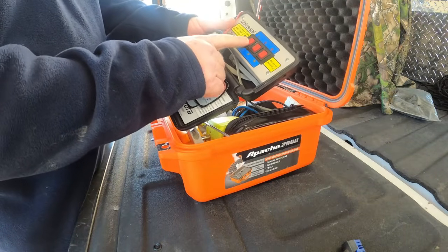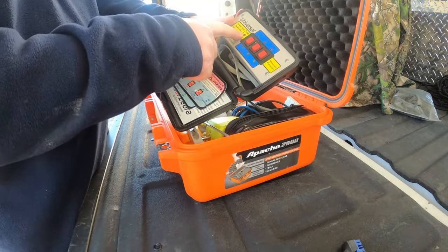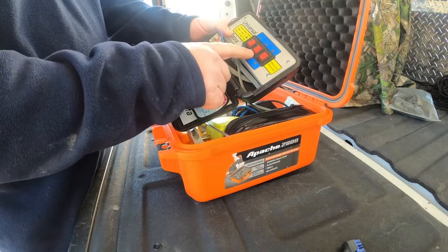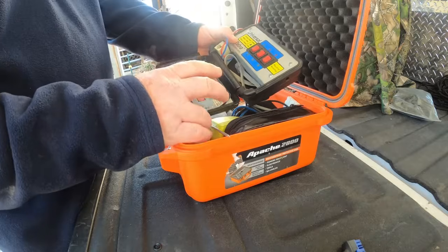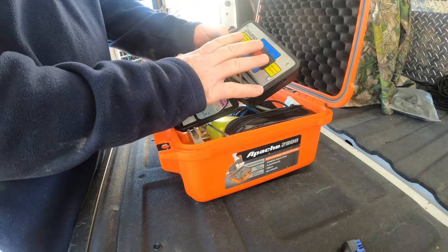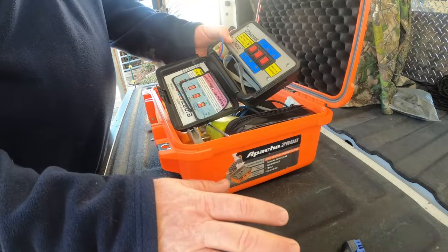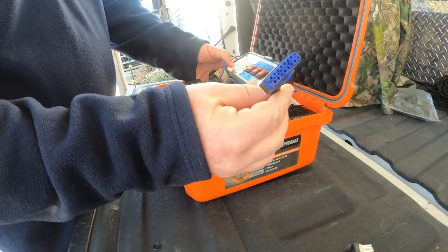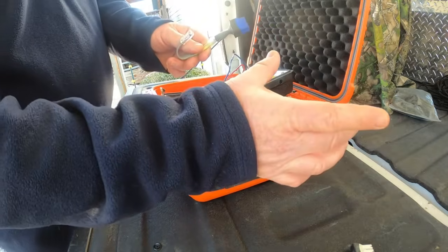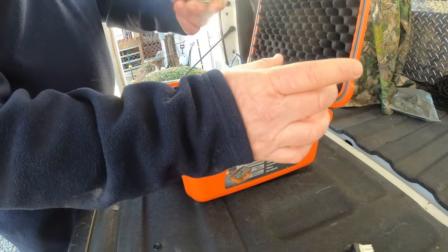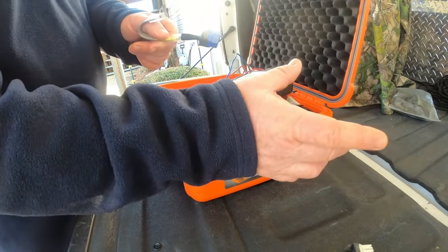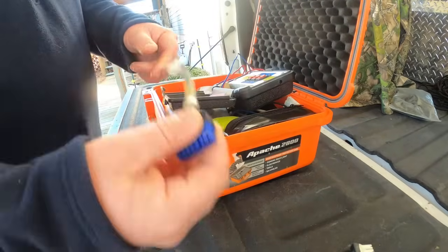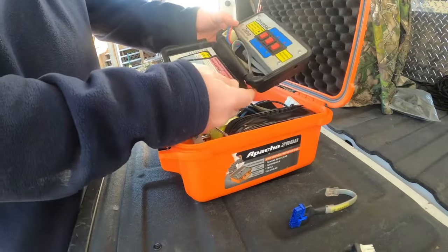Fan on, fan off. When you're connected to your low voltage, this light will come on, and then you can run your fan, you can run your different heat speeds and your different cooling speeds, and you can actually test that motor, determine whether you've got a problem with the motor itself or the control board. In the instance of the 16 pin, typically, especially with Trane, there's going to be a separate ECM or X13 blower control board that the opposite end of this plug is going to be connected to, and then that board is going to energize and send signals for that variable speed motor to ramp up and down. So this is a good tool to have.